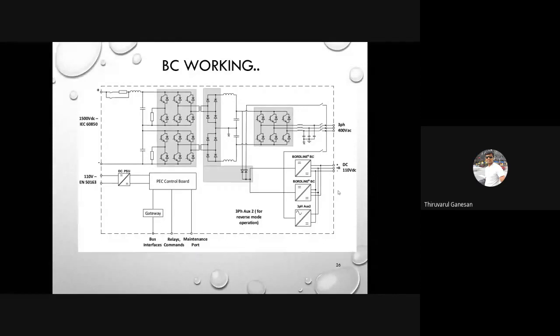Okay, first thing: this is a DC link voltage, and the chopper circuit is not advanced enough to charge the battery. For the battery you have to consider your dV/dt rate, the current rating and the voltage level for each charging state. So for that, we are using two levels of charging system. It is a redundant converter, as I said before. It is customer specific. If a customer asks for a single charger to charge our battery, the charger capacity or power rating will go high.